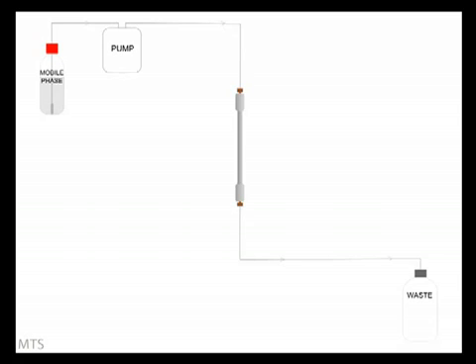Now we have a flow of mobile phase through our stationary phase, but we need a way to introduce the sample for analysis. For this, an injector is required. This instrument is designed to inject a small aliquot of sample, typically in the order of a few microliters, into the flow path of the mobile phase prior to the column. It has to do this without altering or stopping the flow of the mobile phase and thus maintaining the system pressure.